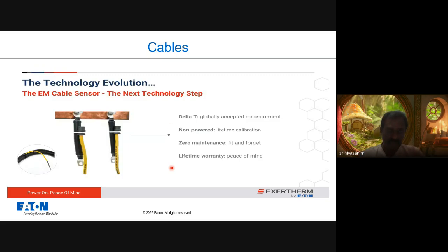In the case of a cable, you can see here this yellow cable with the sensor installed at the top. We can just tie it with the power cables. For example, assume we are taking the MDB incomer, where we have a 630 square mm cable. This is a small cable wire with the sensor, and we can just clip it onto that. If it is placed close to the termination points, we can have accurate values. So it can be installed in new jobs, that means greenfield jobs, and it can also be done in existing brownfield job switchboards.